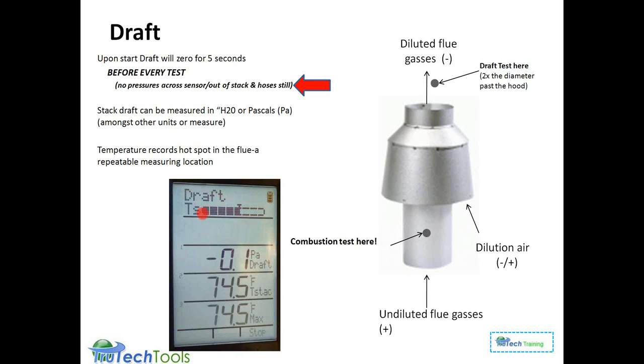The draft test also has a kind of a unique feature where you can find the hot spot in the stack. It shows you the max temperature you've seen, which would be the little tag or T or this arrow mark here, and then the current temperature that you're reading. And then the graphic tells you if you've reached a new level or you found the hottest spot in the stack. The reason for finding that hot spot in the stack is it provides a repeatable measurement location. So the next person doing the test can receive the same value, because draft does actually vary. Again, it's not a perfect world. There's a lot of variations. There's a lot of turbulence, a lot of chaotic airflow inside any part of really a heating or cooling appliance. So you have to have some kind of frame of reference, and this hotspot indicator provides you with that frame of reference.